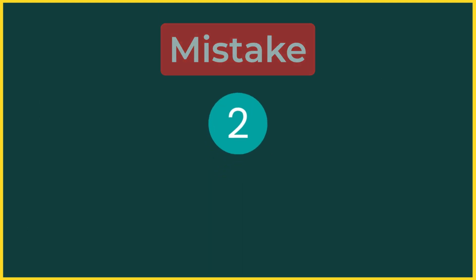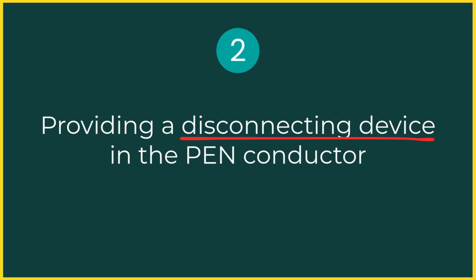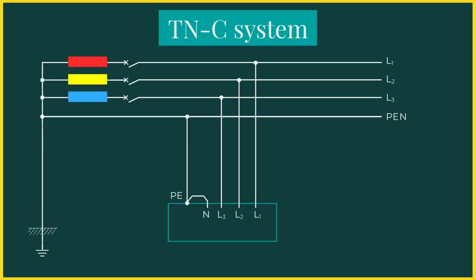Mistake 2. Providing a disconnecting device in the PEN conductor. In a TNC system, there must be no switching or disconnecting devices in the PEN conductor. Any such device would impair the effectiveness of the protective measure known as protection by automatic disconnection of supply. For example, if a switching contact in the PEN conductor fails to close properly, a short circuit to an exposed conductive part may not result in automatic disconnection. As a result, exposed conductive parts could remain energized. For this reason, the PEN conductor must be highly reliable, both electrically and mechanically.